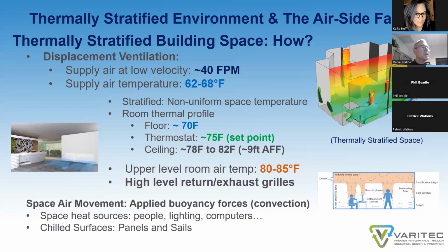Air is injected at about 40 feet per minute. Supply air temperature is 62 to 68 degrees versus 55 degrees in a mixed air system. Why? Well, you don't want to have too cold of air too low on the floor, or people experience cold feet and cold ankles.